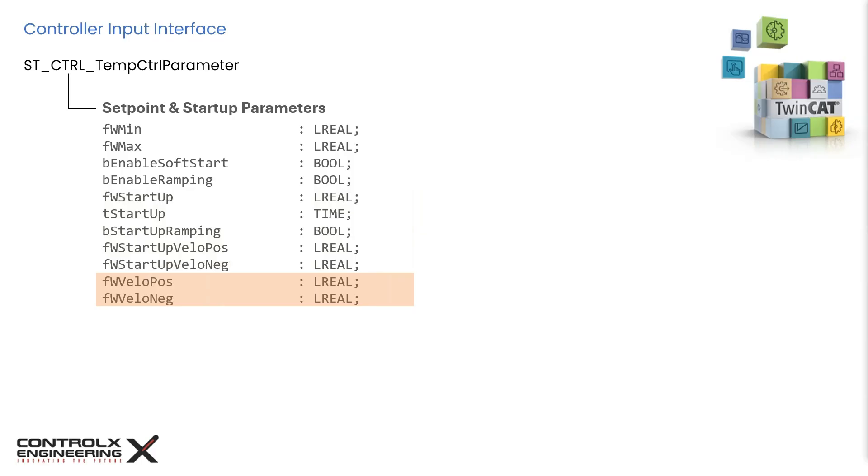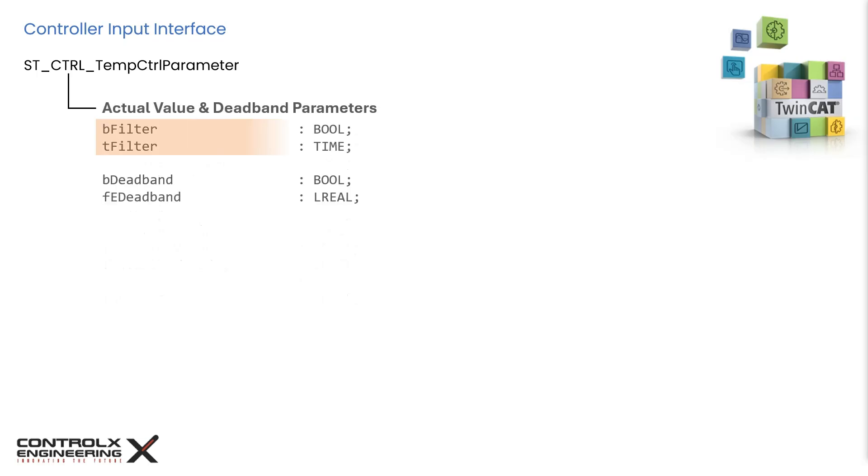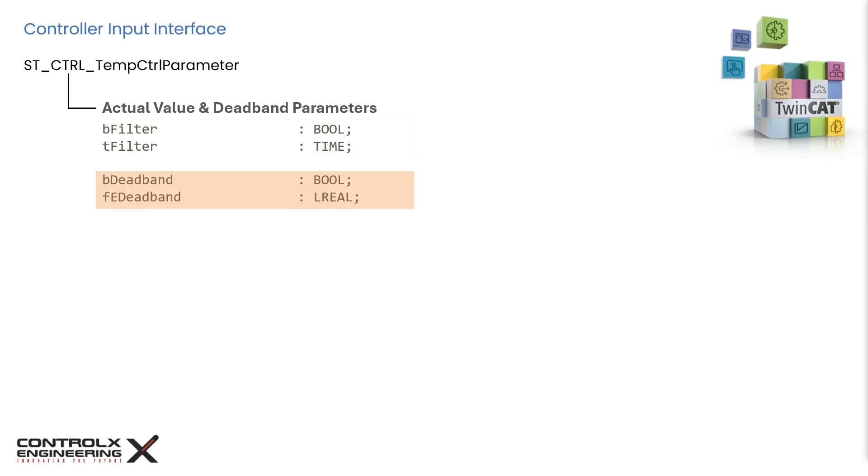For normal setpoints, these two inputs specify the gradient for increasing and decreasing setpoints or rate of rise and rate of fall for the setpoints. Usually, analog signals like the ones we get from the thermocouple for the actual temperature measurement are susceptible to noise. These settings allow a filter to be implemented to smoothen the input signal. The B filter boolean activates the filter for the feedback temperature. And using T filter, you can specify the time constant for the first order filter. These settings allow user to set a deadband in degrees Celsius and the boolean enables or disables the deadband function.